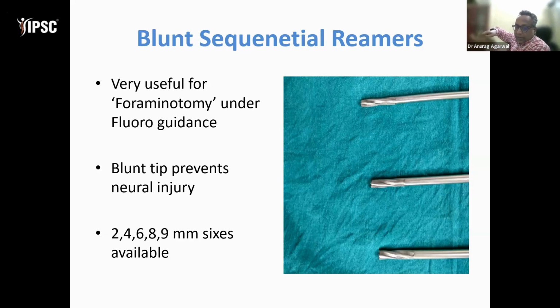And on the downside, this is the disc, so you remove some part of the disc also. You remove the foramen. These equipments are very useful. A few companies make them. Ours, which I am showing you, is the indigenous one. It has a blunt tip and different sizes. The size starts from 4 mm to 6 mm to 8 mm to 9 mm. We use them over the guide wire under C-arm and in a sequential manner to ream the undersurface of the SAP to increase the size of the foramen. So it is very good equipment also.